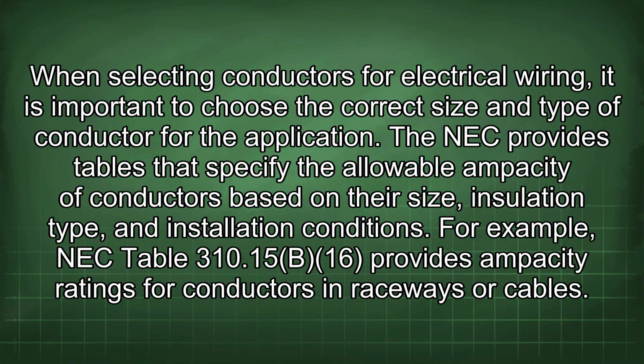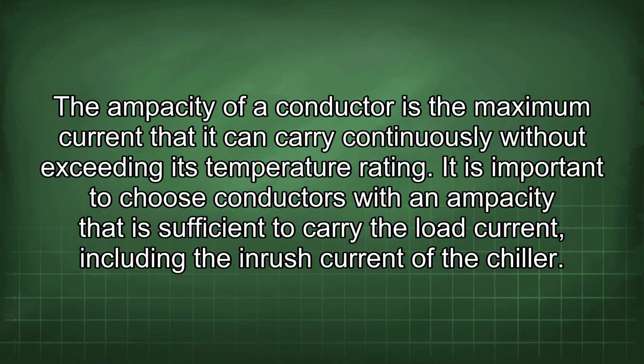When selecting conductors for electrical wiring, it is important to choose the correct size and type of conductor for the application. The NEC provides tables that specify the allowable ampacity of conductors based on their size, insulation type, and installation conditions. For example, NEC Table 310.15(B)(16) provides ampacity ratings for conductors in raceways or cables. The ampacity of a conductor is the maximum current that it can carry continuously without exceeding its temperature rating.